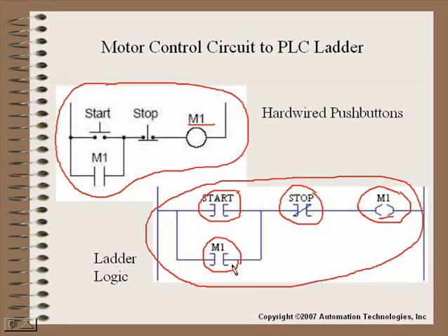Actually, this is not what we like to do. We actually like to take this relay coil, take a contact that would come back from that relay coil, and then enter that into our PLC program. Therefore, we actually have a real-world understanding when we seal our circuit in. And if this relay were to drop out for any reason in the field, then it would also drop our seal in the program.